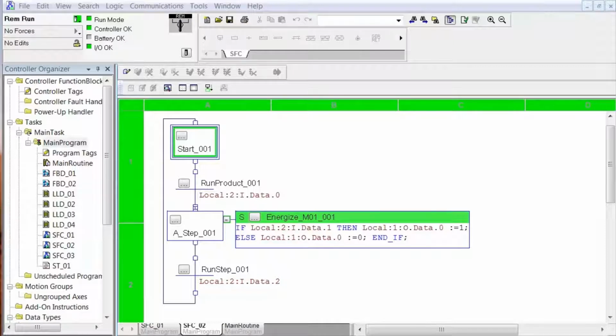Now, if you were going to do this with program control, you would have a JSR in your main program or whatever. And I've mentioned in the past many times that with ladder logic diagram, ladder 2 is the only file that executes automatically when you go in the run mode. If you want to execute ladder 3 through whatever, you have to use a JSR.